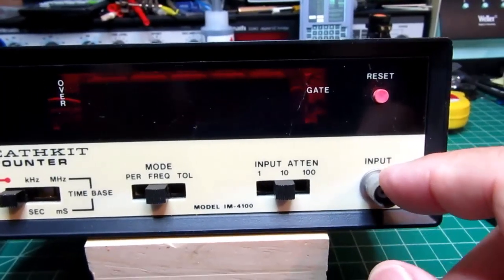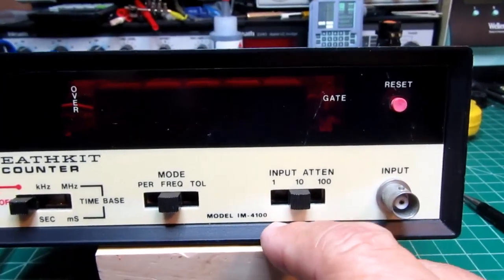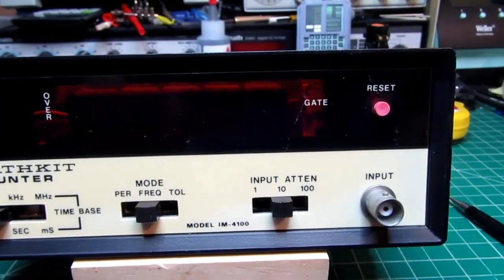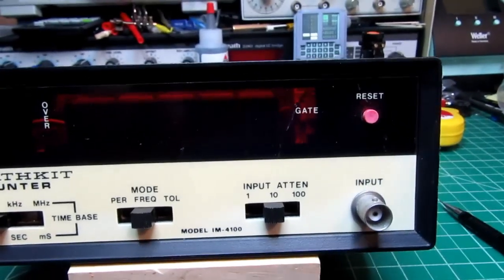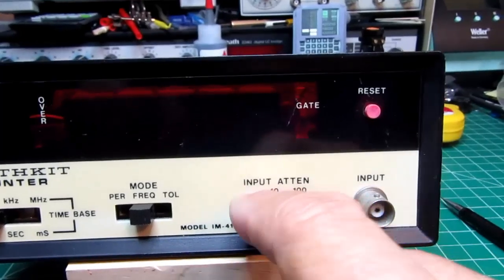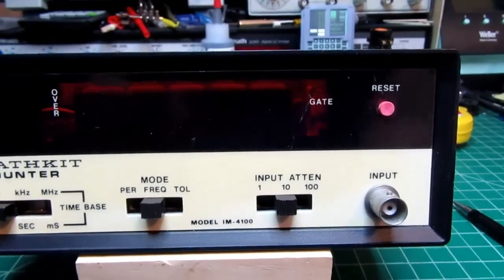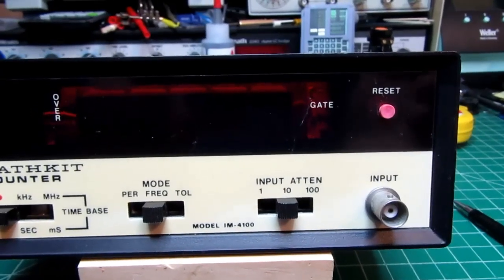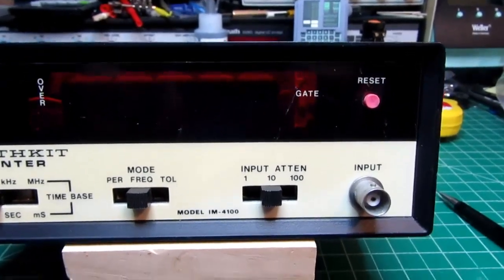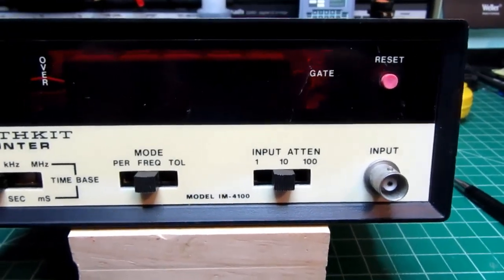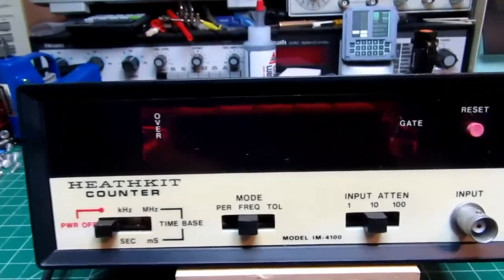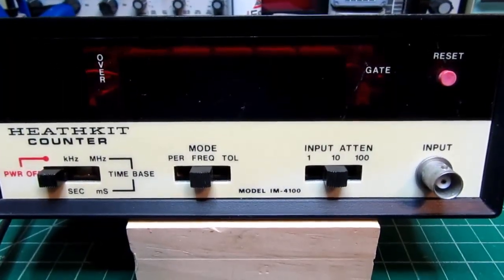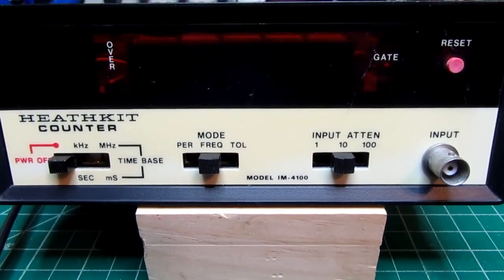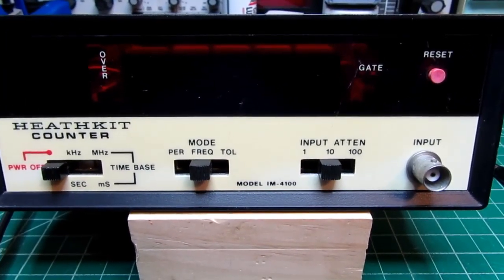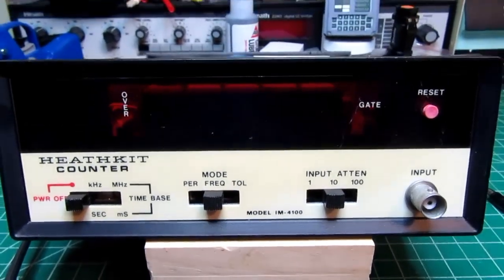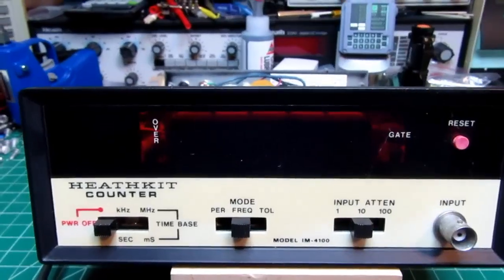Once you get above 100 kilohertz, all the way up to the rated 30 megahertz of this counter, the maximum voltage rolls off fairly sharply. Depending on what your attenuator setting is, it rolls off at a different rate, but regardless, once you get up around 30 megahertz, the maximum voltage is only, I want to say, about 24 volts. I don't have that in front of me, but I think it's about that. So definitely a lot lower than in the lower frequencies. But for most circuits you're liable to use this with, if you're up in the megahertz ranges, your signals probably aren't going to be that high a voltage anyway.